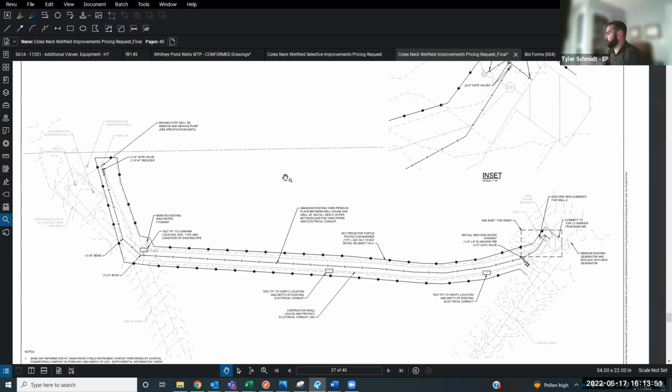Yeah, I can pull some numbers together for you specifically. I did a hydraulic analysis a little while ago, but I don't have that in front of me right now. I don't want to give you the wrong numbers, but generally speaking, with a 4-inch pipe, once you get over 200 gallons a minute, you start hitting significant head losses.